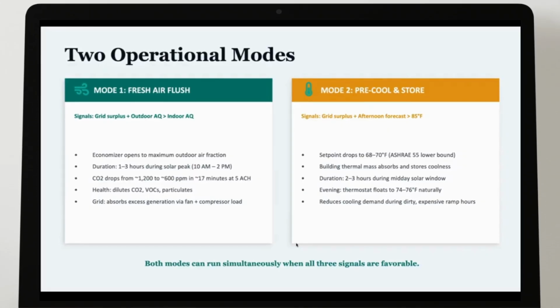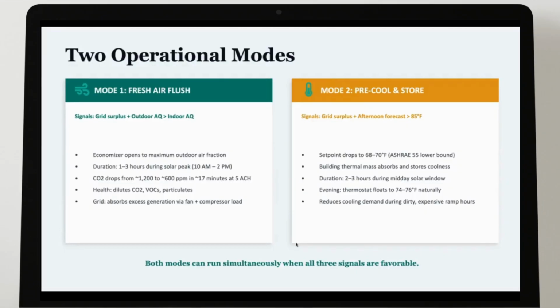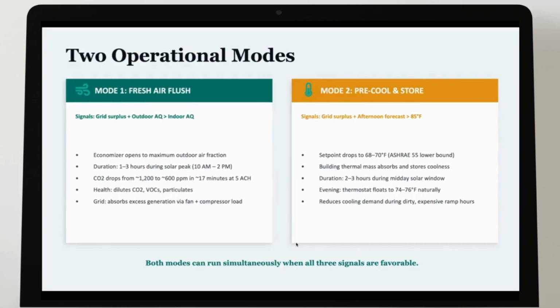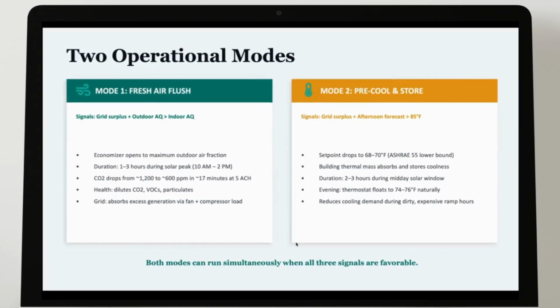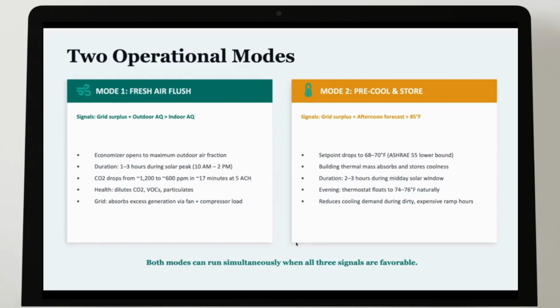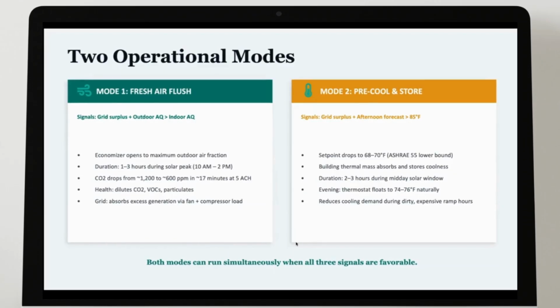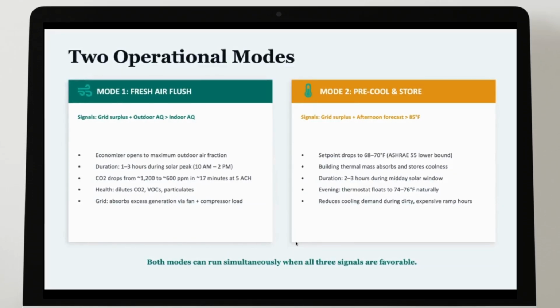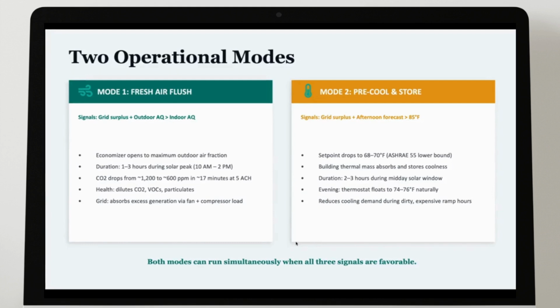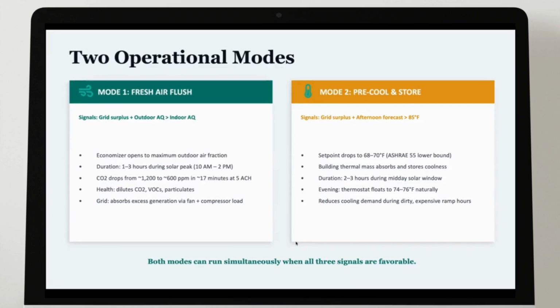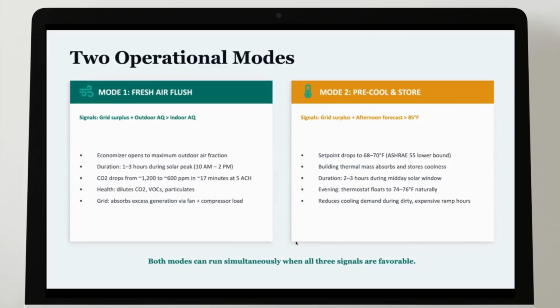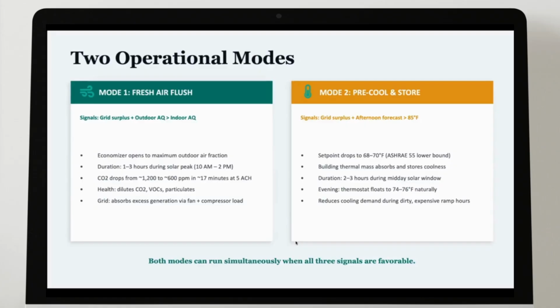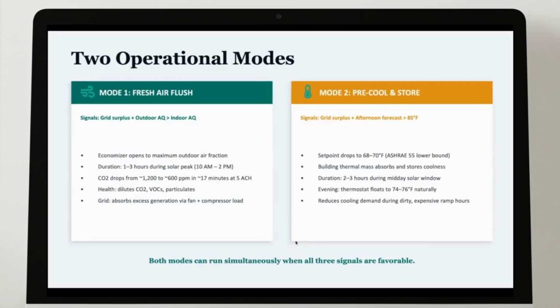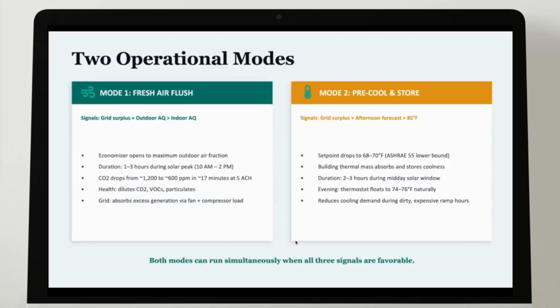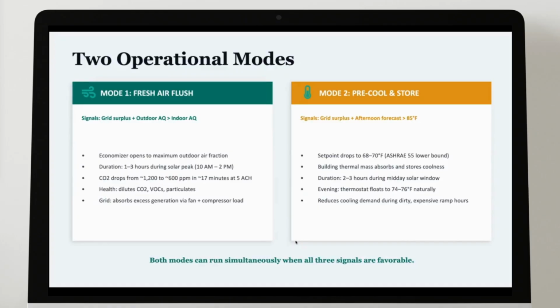The pre-cool and store idea: during lunchtime, occupancy rate of the building lowers, so you can cool the building an extra couple of degrees knowing you'll have to cool it again in 2-3 hours. People come back, the thermostat floats back up, and it evens out that curve a bit.